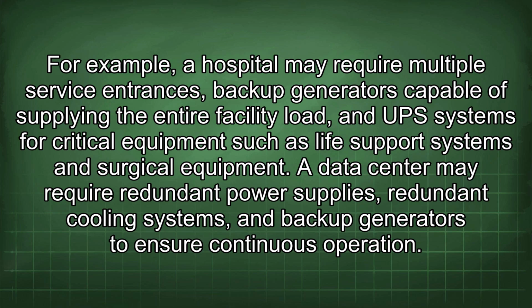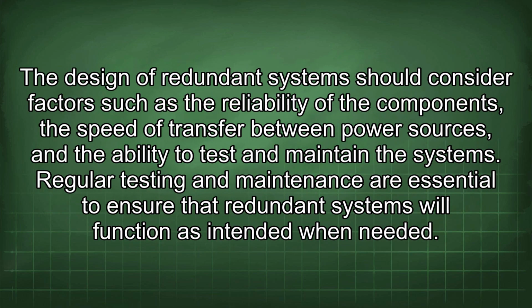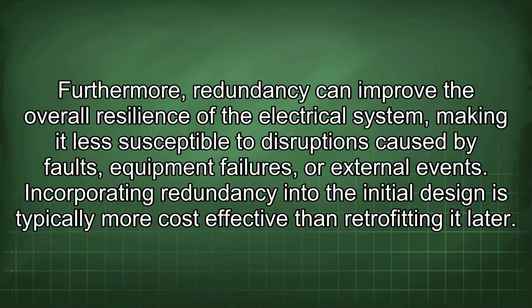A data center may require redundant power supplies, redundant cooling systems, and backup generators to ensure continuous operation. The design of redundant systems should consider factors such as the reliability of the components, the speed of transfer between power sources, and the ability to test and maintain the systems. Regular testing and maintenance are essential to ensure that redundant systems will function as intended when needed. Furthermore, redundancy can improve the overall resilience of the electrical system, making it less susceptible to disruptions caused by faults, equipment failures, or external events.